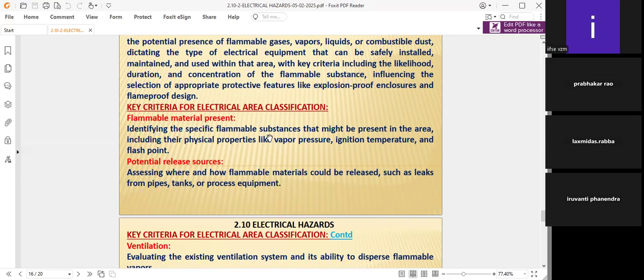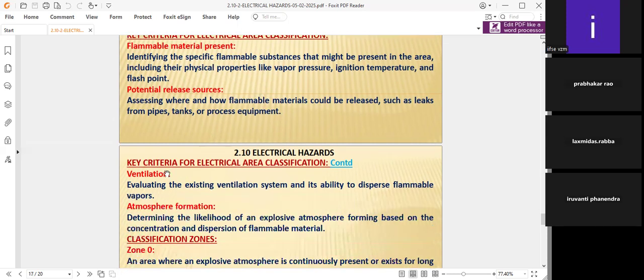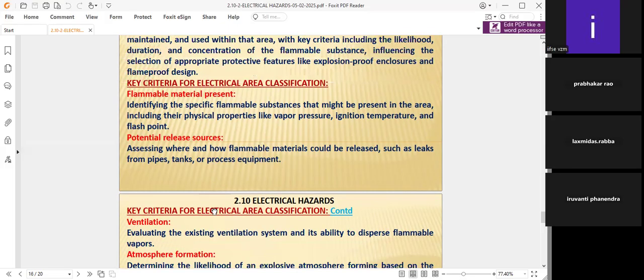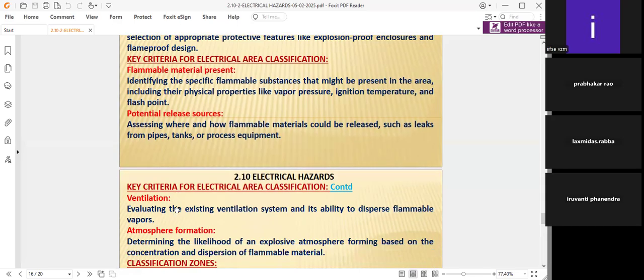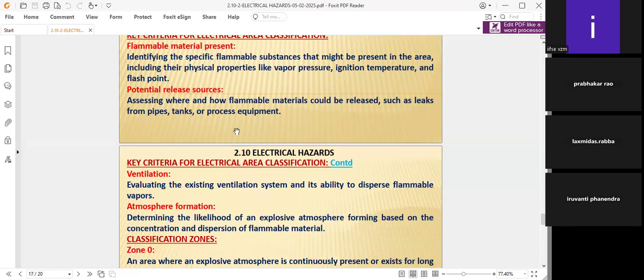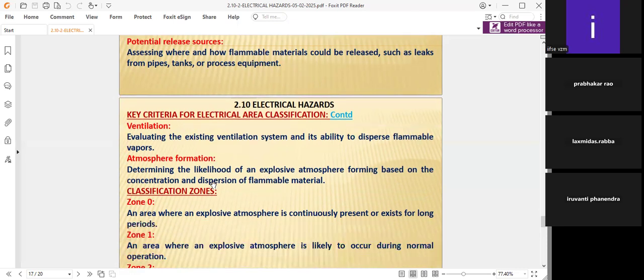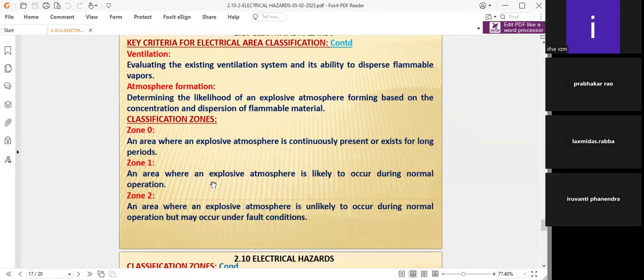That is why there are criteria for electrical area classification. One is whether the area has flammable materials or a potential release of sources, and these are separated with respect to ventilation and atmosphere formation. The criteria for electrical area classification depend upon the flammable materials, the potential release of sources, the ventilation, and the atmosphere formation. These things decide the risk level identification, whether the classification comes under zone 0, zone 1, or zone 2. These are the three very important areas.